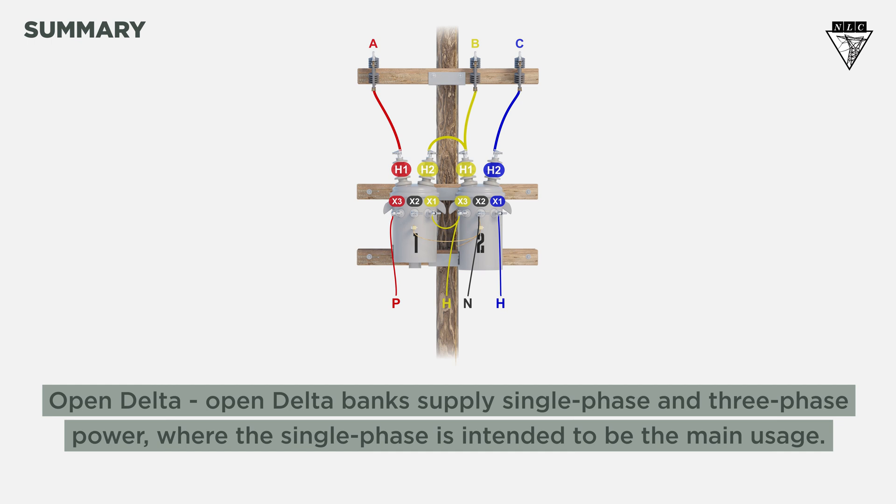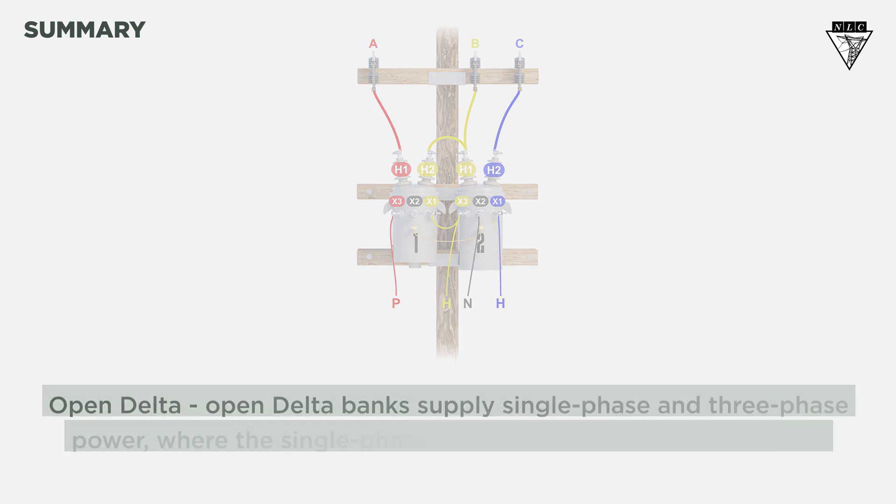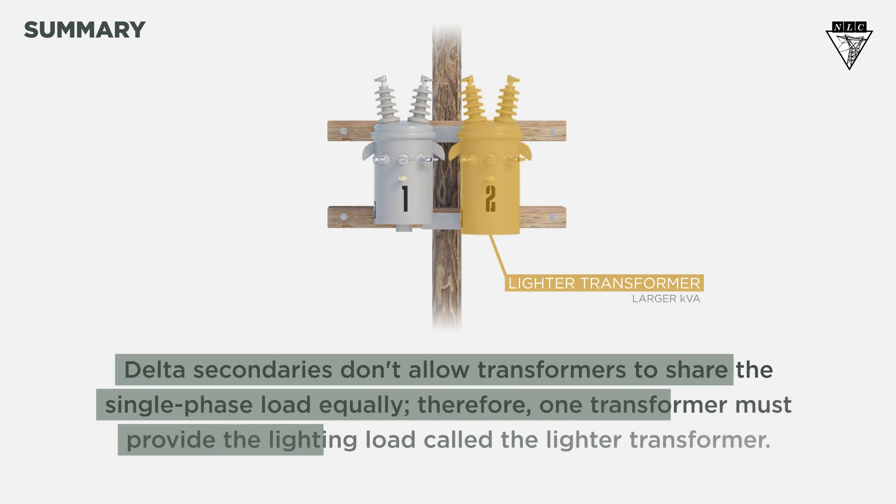So, what did we learn? Open-delta open-delta banks supply single-phase and three-phase power, where the single-phase is intended to be the main usage. Delta secondaries don't allow transformers to share the single-phase load equally. Therefore, one transformer must provide the lighting load, called the lighter transformer.